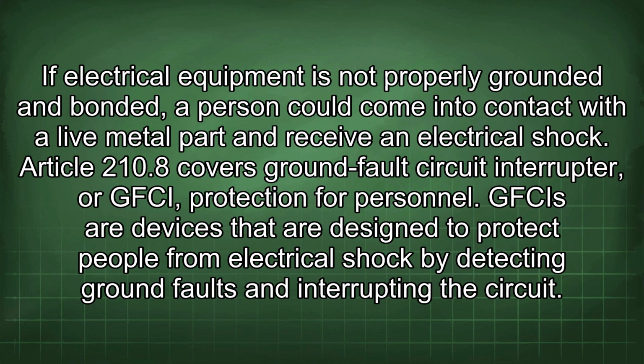If electrical equipment is not properly grounded and bonded, a person could come into contact with a live metal part and receive an electrical shock. Article 210.8 covers ground fault circuit interrupter, or GFCI, protection for personnel. GFCIs are devices that are designed to protect people from electrical shock by detecting ground faults and interrupting the circuit.